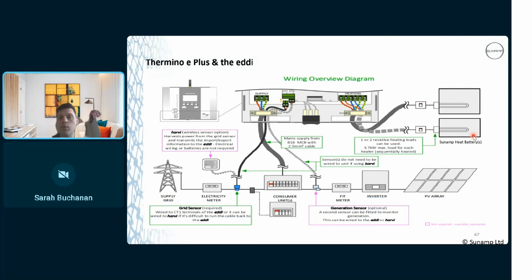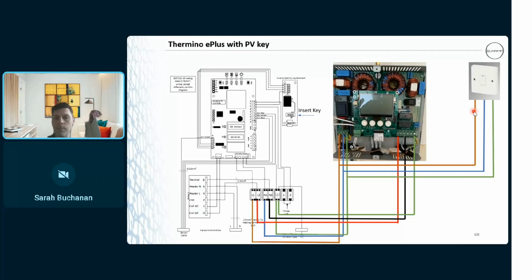The only thing you'd have to consider with plumbing them in series, though, is the pressure loss across the heat exchangers. The reason with a PV configuration, if you have them plumbed in parallel, your primary battery is going to reach temperature first, and then your secondary battery. But if your secondary battery is not up to temperature, then that may give you a cold influx of water and start affecting the outlet temperatures. So that's the reason why. In a grid electric sense, yeah, you can fit these in parallel quite happily. As long as the timings are the same, or if there's no timer, even better, they'll just be charging constantly up to temperature. So you shouldn't get any cold influx of water.